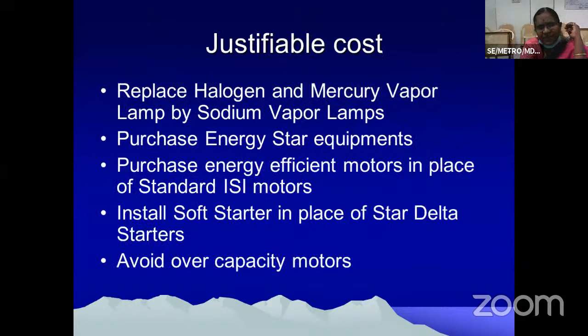At justifiable cost, replace all halogen and mercury vapor lamps with sodium vapor lamps. Purchase Energy Star equipment. Purchase energy efficient motors in place of standard ISI motors. Install soft starters in place of star delta starters. Avoid overcapacity motors. This we are experiencing in most of the industries. They can install motors to the capacity that is required.